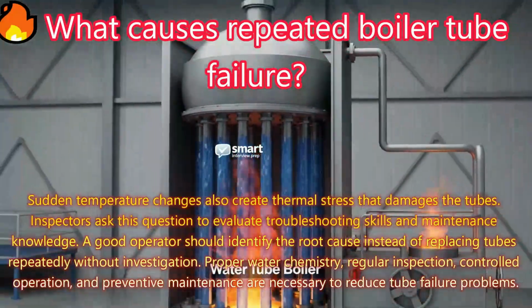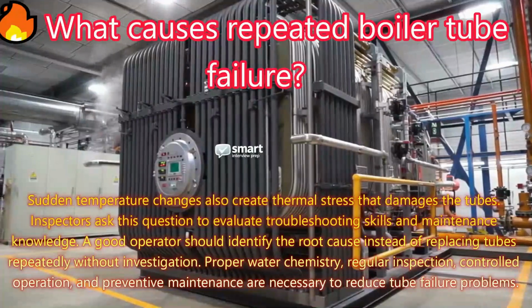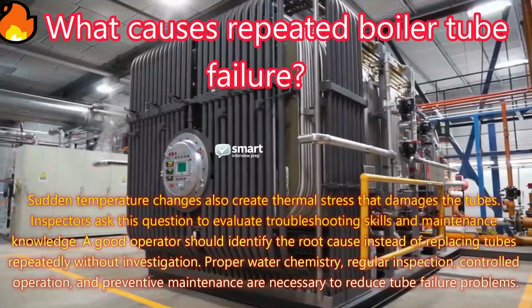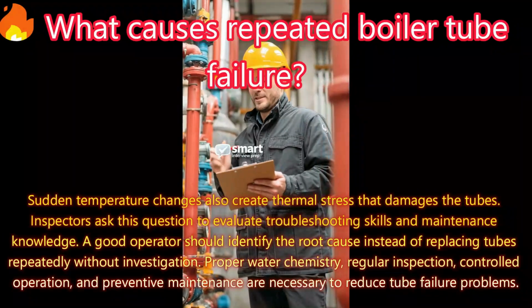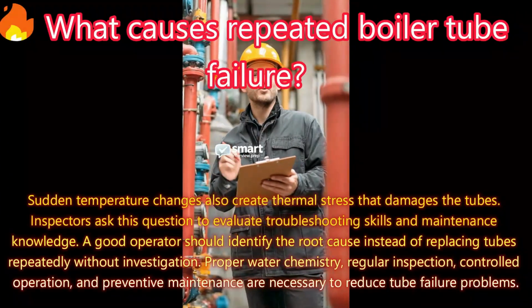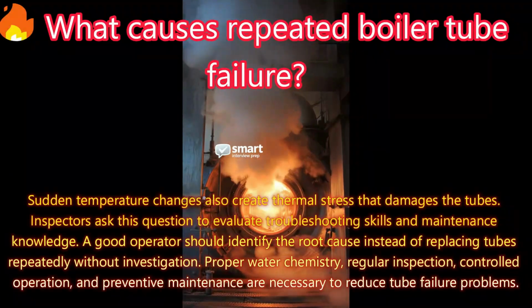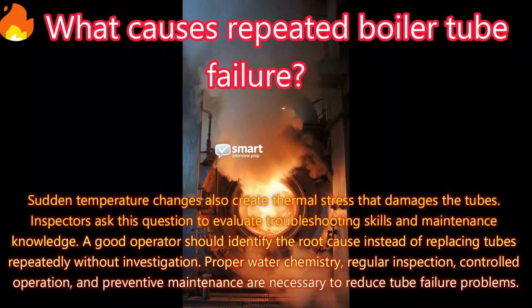Inspectors ask this question to evaluate troubleshooting skills and maintenance knowledge. A good operator should identify the root cause instead of replacing tubes repeatedly without investigation. Proper water chemistry, regular inspection, controlled operation, and preventive maintenance are necessary to reduce tube failure problems.